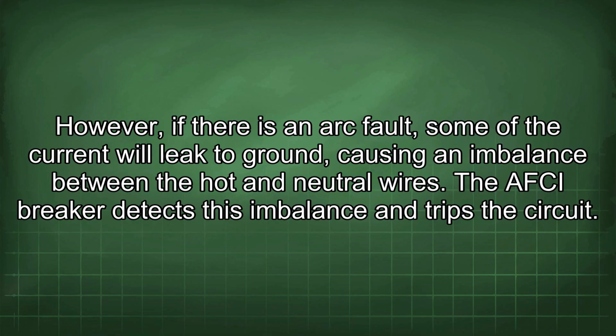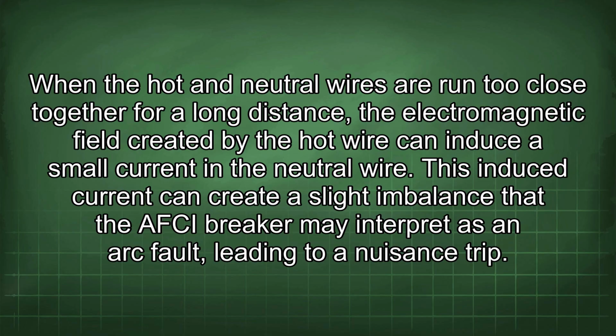However, if there is an arc fault, some of the current will leak to ground, causing an imbalance between the hot and neutral wires. The AFCI breaker detects this imbalance and trips the circuit. When the hot and neutral wires are run too close together for a long distance, the electromagnetic field created by the hot wire can induce a small current in the neutral wire. This induced current can create a slight imbalance that the AFCI breaker may interpret as an arc fault, leading to a nuisance trip.